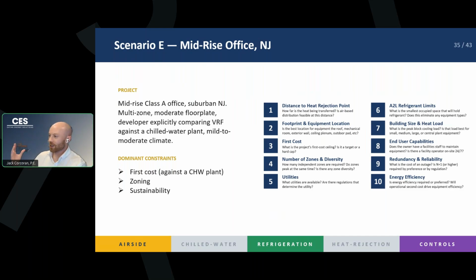Let's say this owner all of a sudden thinks, I don't want to go with A2L anymore. That means you automatically have to go with your chilled water. But let's say the owner says, I don't want to give up any rentable floor space to a chiller plant, stick everything on the roof, then we have to go with VRF. So this is a situation where it could maybe sway either way, but it depends on the exact situation that you're dealing with. Maybe you need to ask some more questions after narrowing down your fields to these two pieces of equipment.